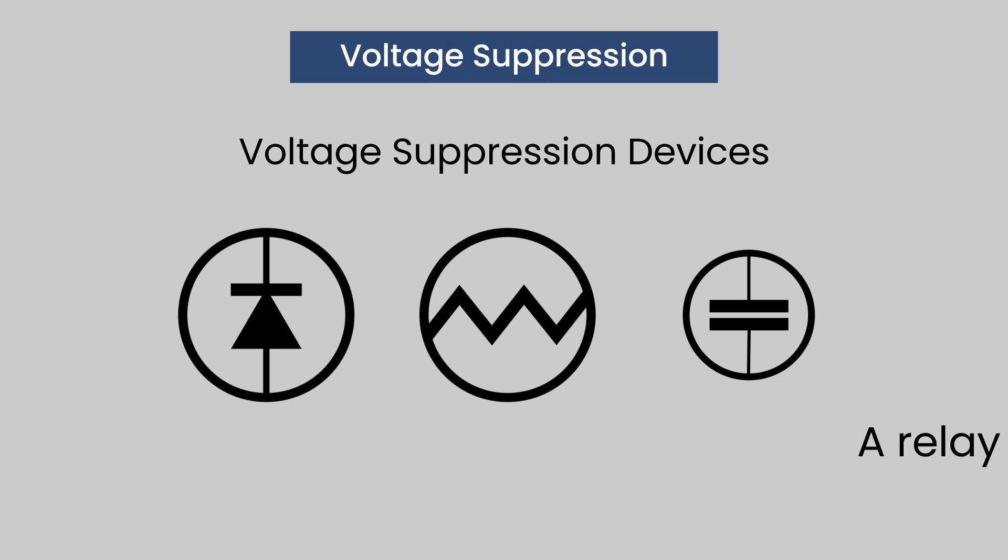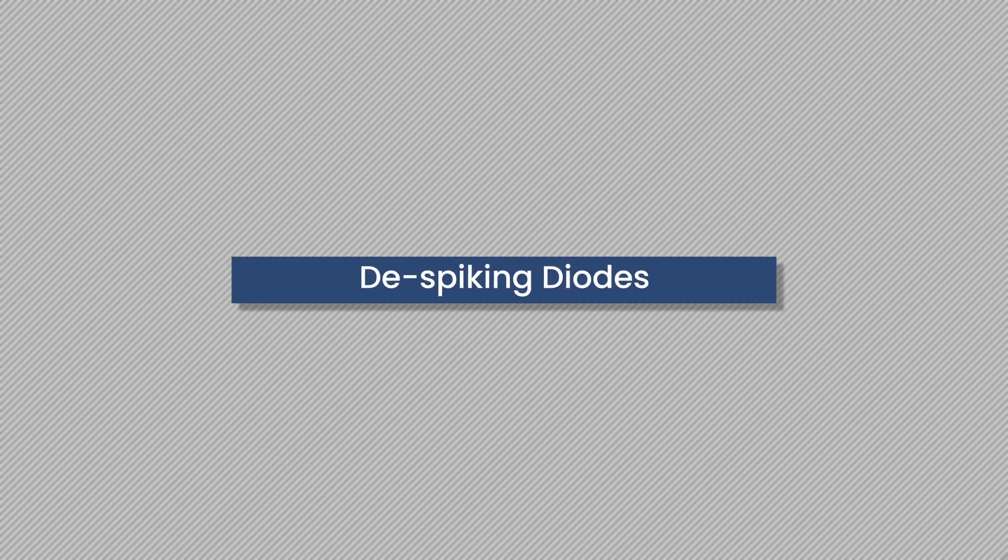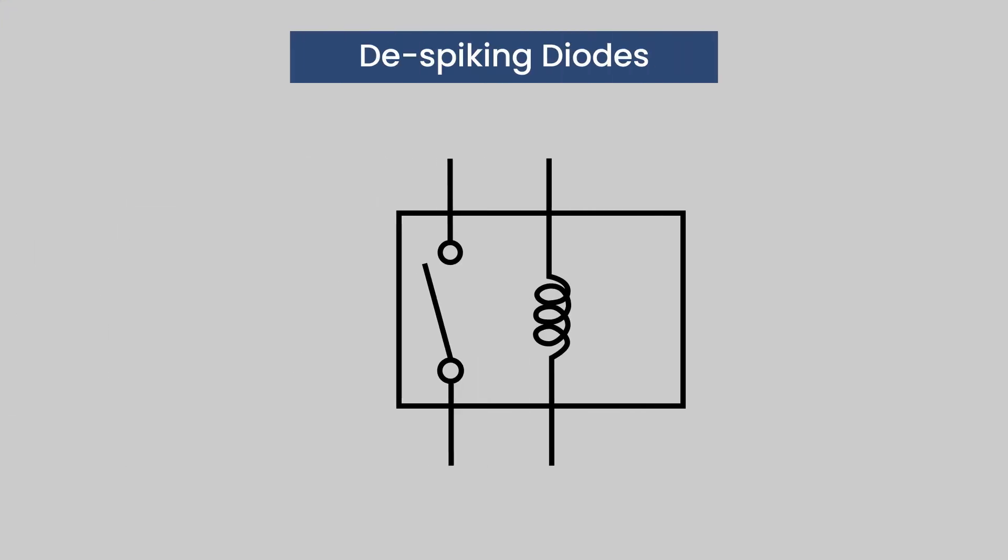A relay will be clearly marked if one of these is present. Relays with despiking diodes: a despiking or clamping diode is connected in parallel with the relay coil. When the relay is on, this diode will be in reverse orientation so that no current will flow through the diode.